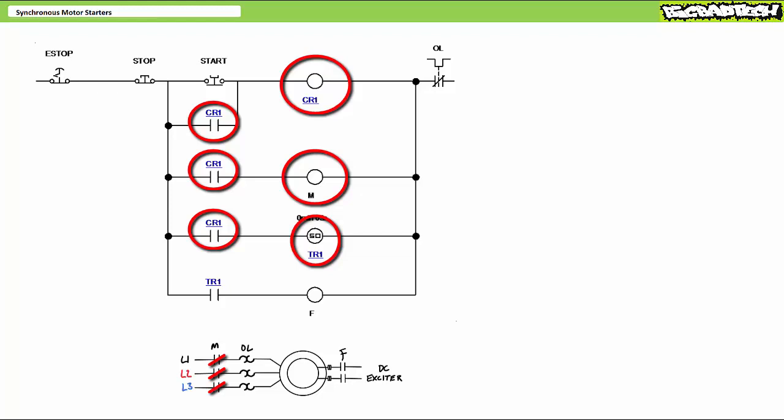Three seconds later, the timer completes the on-delay function. TR1 in rung 5 changes state and energizes the F contactor coil. The field contactor closes and energizes the rotor field, which locks into the stator's rotating magnetic field, suitable for constant speed operation characteristic of a synchronous motor.